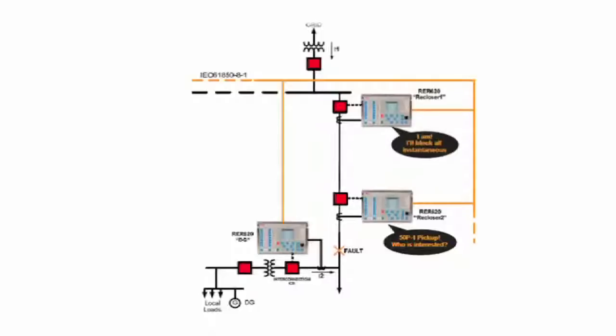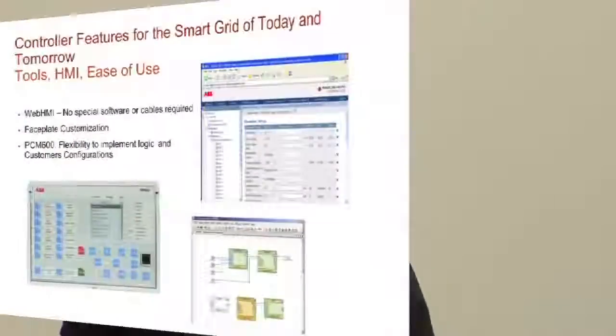Your operators most likely will be downloading events, so they go to that tab, or downloading oscillography records, and it obviously has different access levels. If it's an operator, it allows you to read and download records, but it doesn't let you change settings. If you're an engineer, it allows you to change settings, but it doesn't let you operate the recloser. So there are different access levels that you could provide. But again, the key is that it doesn't need any special software or special cables, and it helps you increase the speed with which you can connect to a unit, troubleshoot your network, and get your customers back up and running a lot quicker.